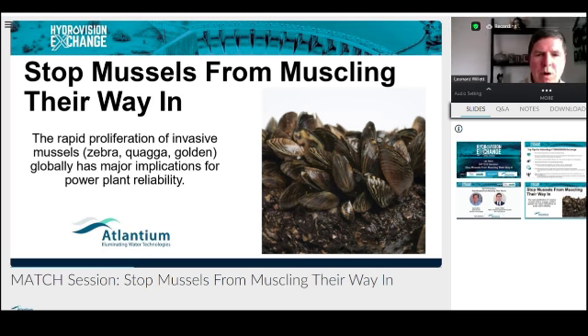So when the mussels arrived, what ended up happening is the heat exchangers would start to biofoul. Once the heat exchangers biofouled, the control room operators would get a high temp alarm, and the facility managers were concerned that these high temp alarms would cause forced outages. As anybody in hydro knows, forced outages have huge costs to them.